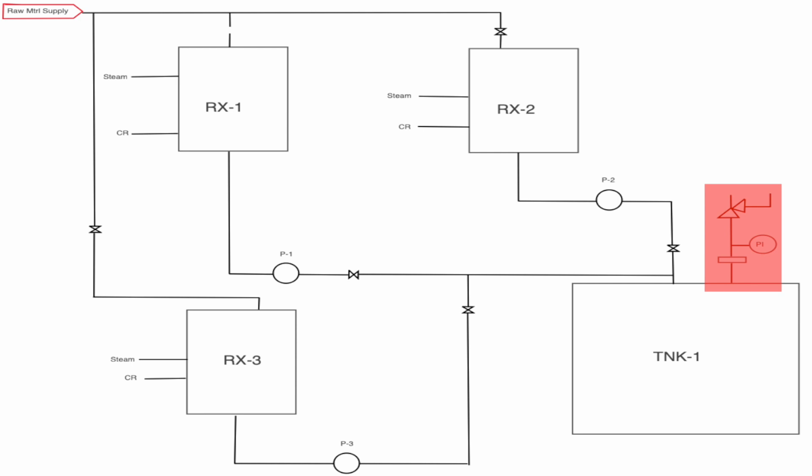It's going to send an alarm to some sort of DCS or safety manager system to let you know that you are having issues with your rupture disc. The benefit there is you then don't have vapor with entrained liquid or liquid itself, depending on the scenario, coming in contact with that relief device all the time and potentially creating an issue with the relief device when you actually need it to work.